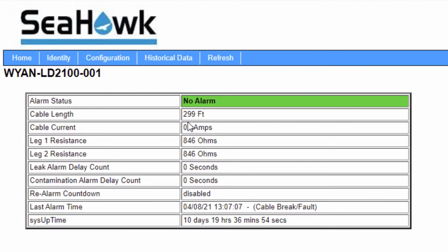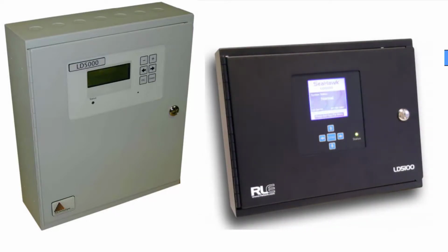Now we can see that it's showing about 299. Refresh. Like I said, there's a little bit of oscillation in here, this going up and down, but when you start getting into having thousands of feet hooked onto your controller, this can make a big difference for your pinpoint accuracy. So on older models like the LD5000 series or the LD5100 that didn't have a web interface, you could actually make these adjustments to the ohms per foot through the front local display on that controller.